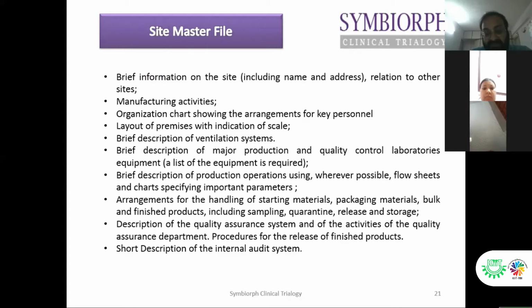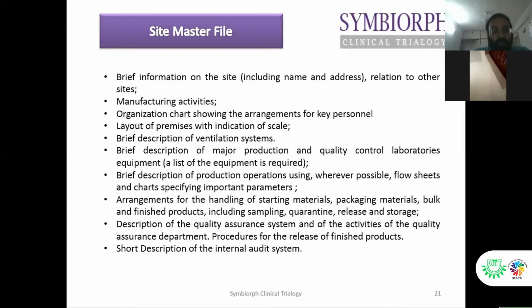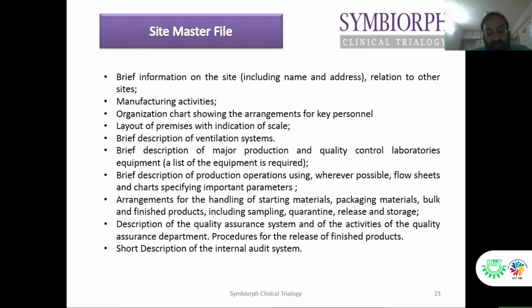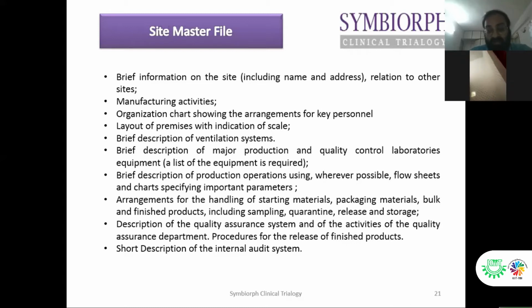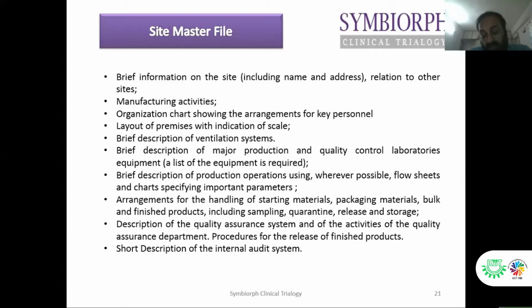You have to write brief information about the site, including the name and address, and what manufacturing activities you are going to do at the site. You have to prepare an in-depth organization chart with the detailed roles and responsibilities of the persons involved, and the layout of the premises with an indication of scale. You have to have a layout of the premises showing where you are going to manufacture, and the class of the different areas. You have to demarcate whether it's class 10,000 or class 1 lakh, depending upon the device which you are manufacturing. Many medical devices might not need a clean room requirement. They only need a well-ventilated area. All that you have to define in the plan layout.